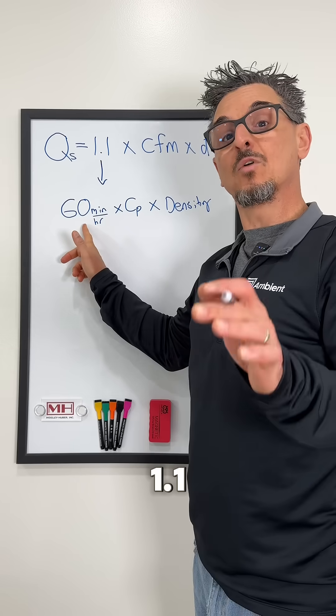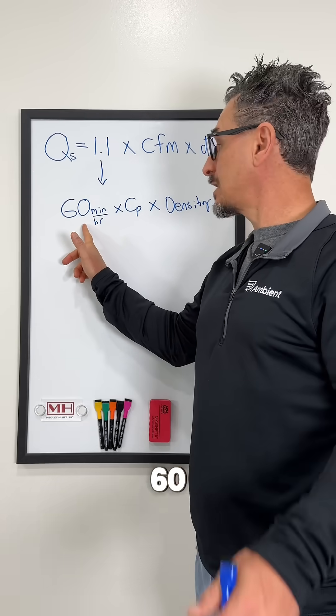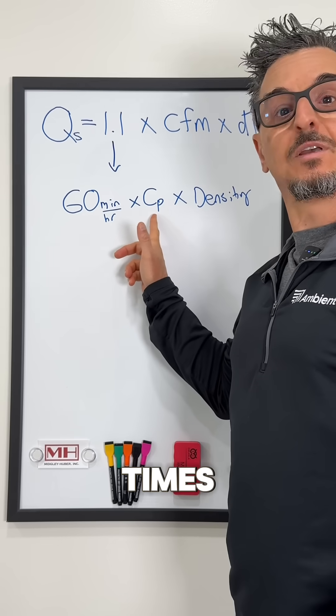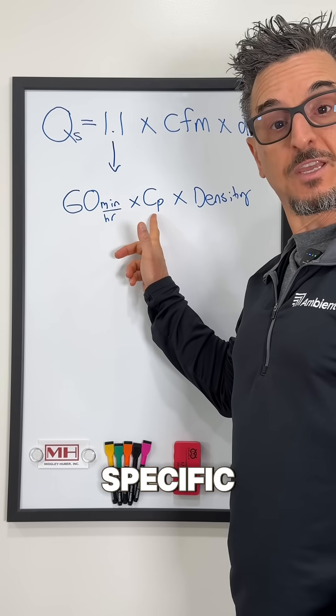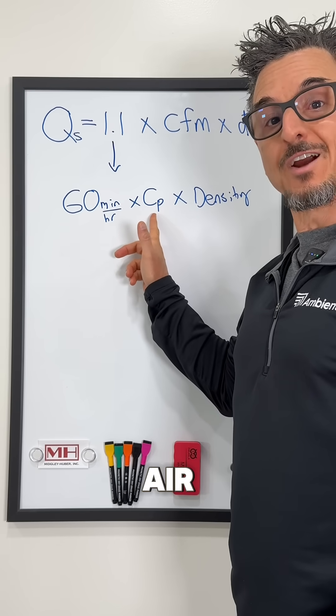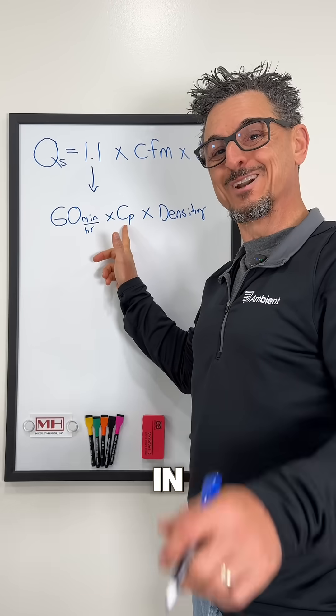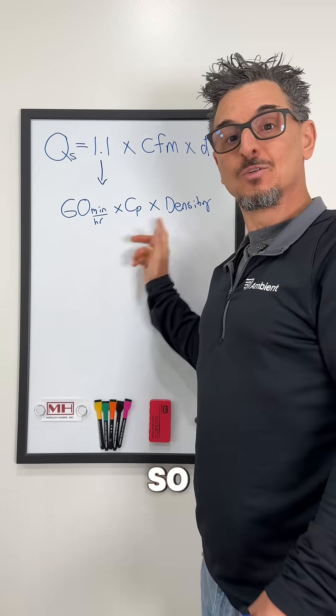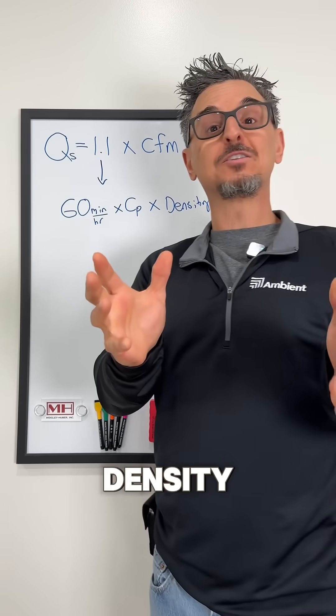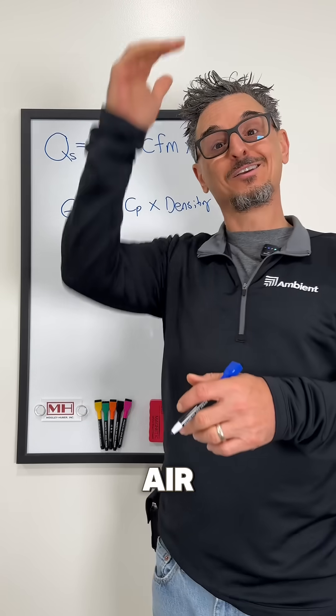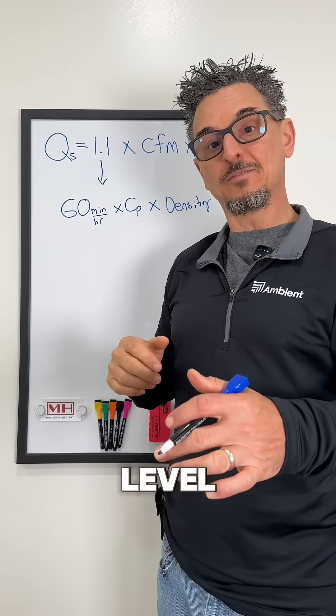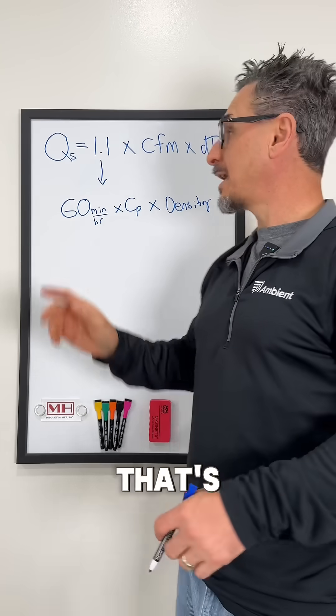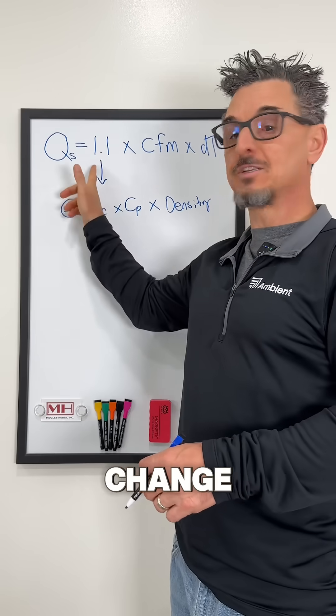The 1.1 breaks down as 60 minutes per hour times the specific heat of air — we'll get into that in another video — times the density of air. What do you know about the density of air up in the mountains versus at sea level? It's a lot lower, so that's obviously going to change this number.